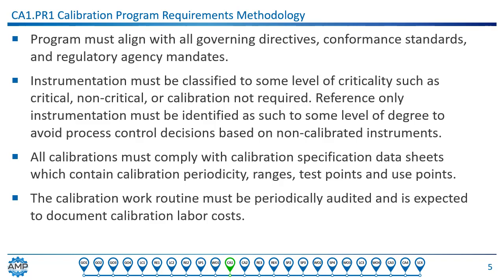The purpose of calibration program requirements is to ensure the necessities for setting up a calibration program are known and adhered to. The program must align with all governing directives, conformance standards, and regulatory agency mandates. These can vary by location and industry, but are typically easy enough to identify and apply within a well-constructed program. All instruments that need to be calibrated must be identified, and instrumentation must be classified to some level of criticality, such as critical, non-critical, or calibration not required. This aids in correctly classifying discrepancies or deviations as critical or not.